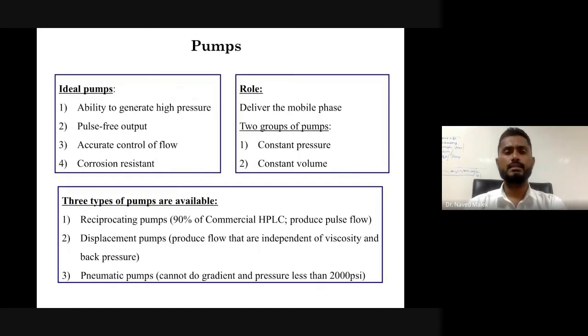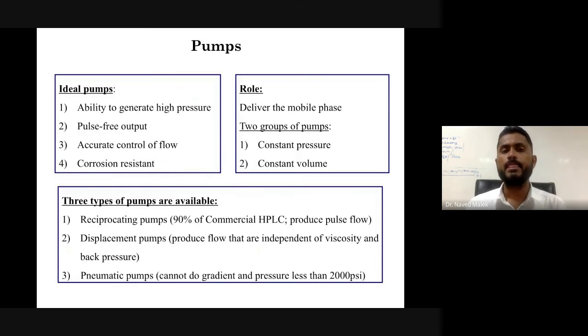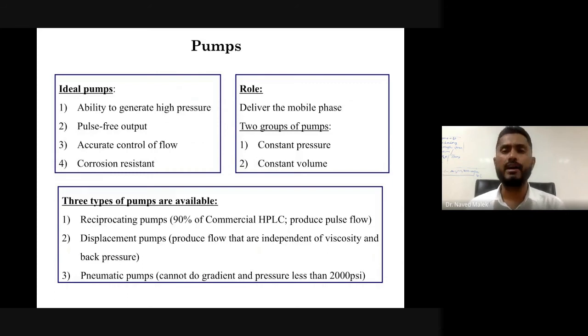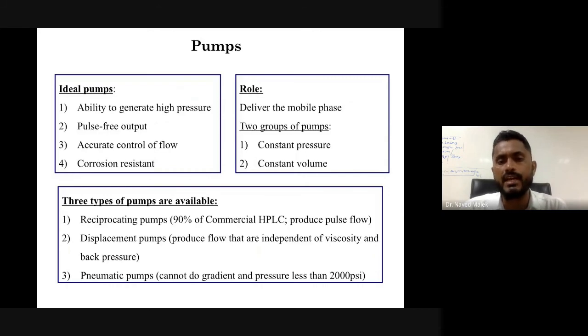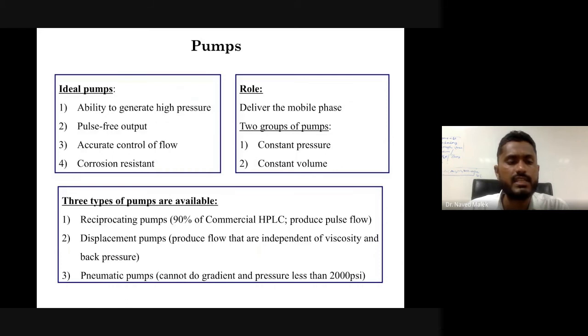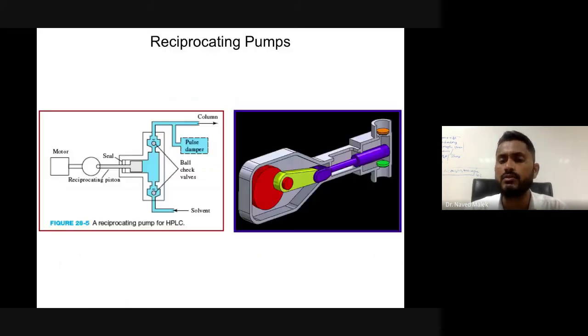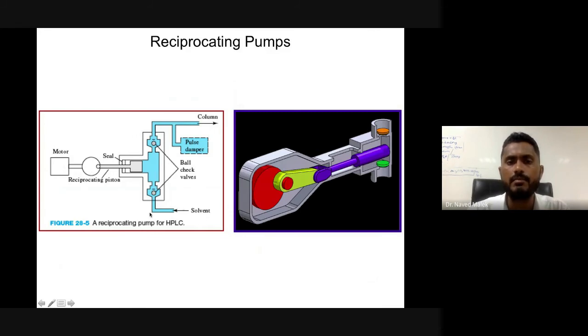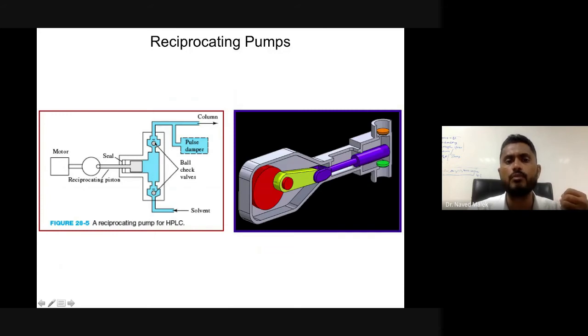HPLC pumps must be able to generate high pressure, provide pulse-free output, allow accurate control of flow, and be corrosion-resistant. Their role is to deliver the mobile phase. Three types of pumps exist: reciprocating pumps (used in 90% of commercial HPLC, produce pulsed flow), displacement pumps (flow independent of viscosity and back pressure), and pneumatic pumps (cannot do gradient and limited to below 2000 psi). In a reciprocating pump, a piston reciprocates — ball check valves open to allow solvent in, and the piston then forces the mobile phase towards the column at high pressure.